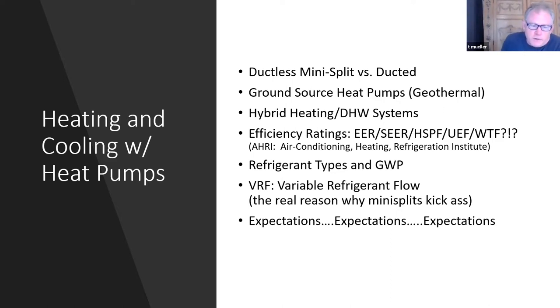We've all experienced an air conditioning system with two stages - it comes on and then shifts into high gear, a two-speed system. Well, these systems are not that. They have a variable speed, so they can go through the full spectrum of speeds. The way they accomplish this is a little complicated, but essentially there's an inverter in the system which converts the power source from AC to DC, and then the components run on a DC electrical system, giving a full range of speed for the condenser.